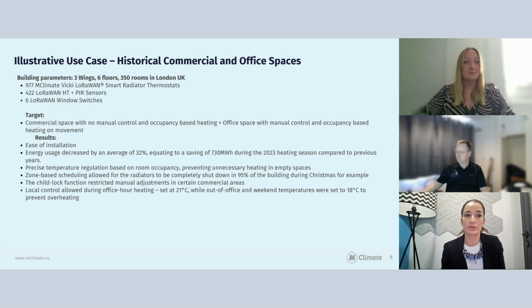We have over 900, almost 1,000 TRV radiator devices. And half of those rooms also have an HT and PIR sensor, which is detecting movement in the morning to optimize the scenarios. We have some window switches as well, which are quite interesting, just to optimize the workings of the system. We actually stop heating the rooms when we have window open detection in place. The target for the project was to optimize the commercial space and the office space being used. Some of it is used for events, others for recurring exhibitions. Different office spaces are occupied at different times.